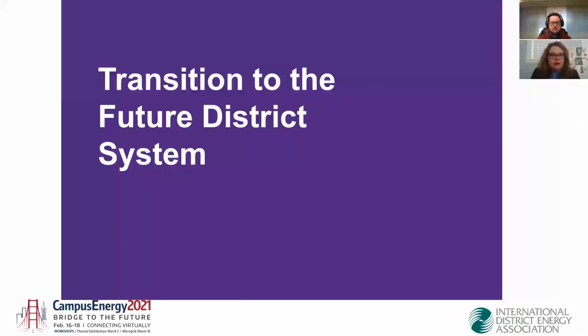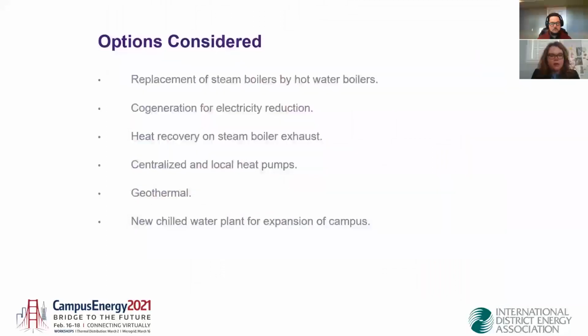How do we take that existing system and bring it to the future without having too much capital cost and, of course, reducing energy and GHG emissions? So many options were considered. For example, the replacement of steam boilers by hot water boilers. So that implied replacing almost all of the piping. Some portions could be reused, but with high pressure steam the diameter is smaller, so portions of pipes had to be completely removed and replaced. So capital cost was really high for that option.